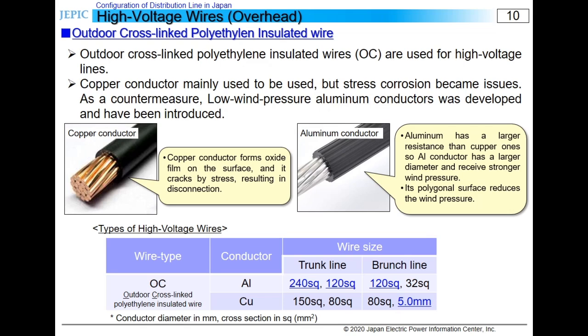Aluminum is unlikely to rust, so stress corrosion is prevented, but it has a larger resistance than copper, so the diameter of the conductor becomes larger. Then its wind pressure also gets stronger. Low wind pressure wire has a polygonal surface so that its wind pressure can be reduced. The table shows the types of wires used in the Hokuriku area, and the ones in blue are currently used as standards.